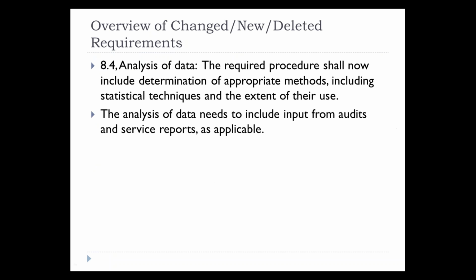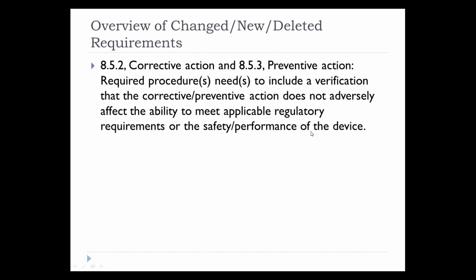8.4, analysis of data. The required procedure shall now include a determination of appropriate methods, including statistical techniques and the extent of their use. And the analysis of data needs to include input from audits and service reports as applicable. 8.5.2, corrective action, and 8.5.3, preventive action. Again, still requirements for procedures, and these procedures need to include a verification that the corrective or preventive action does not adversely affect the ability to meet applicable regulatory requirements or the safety performance of the device.